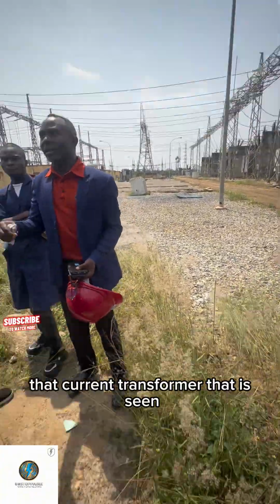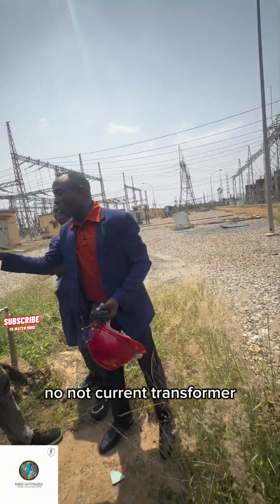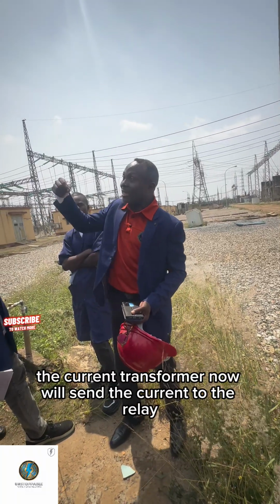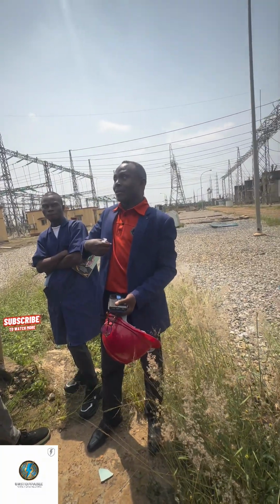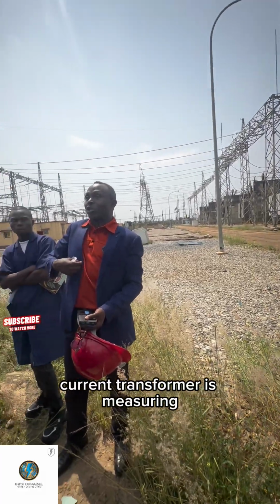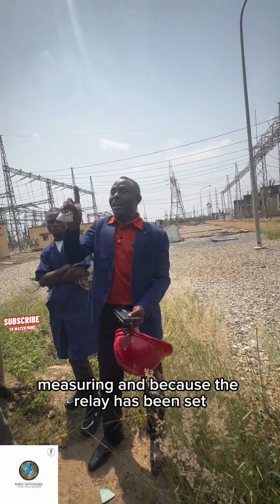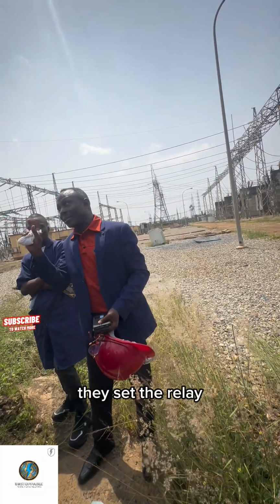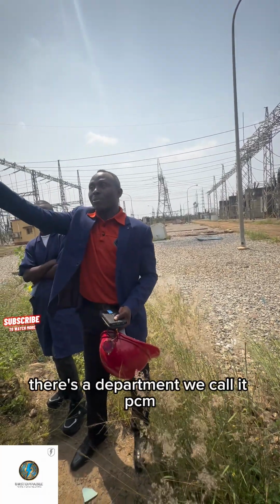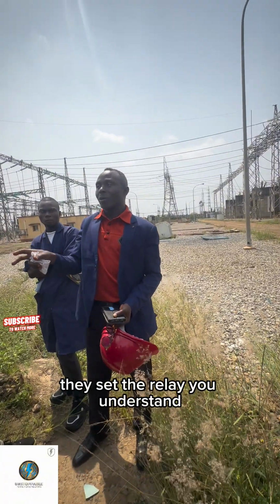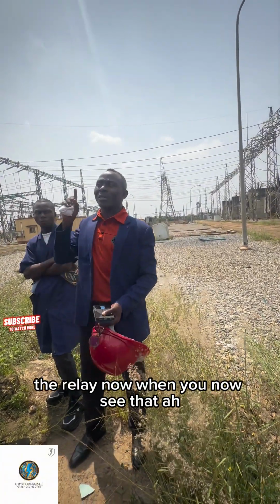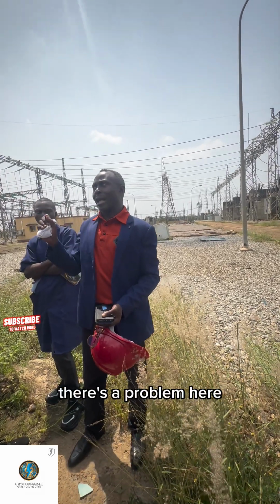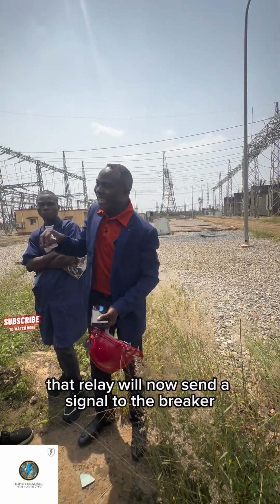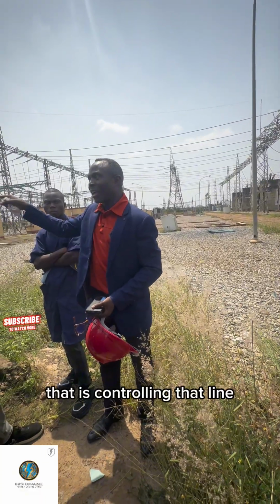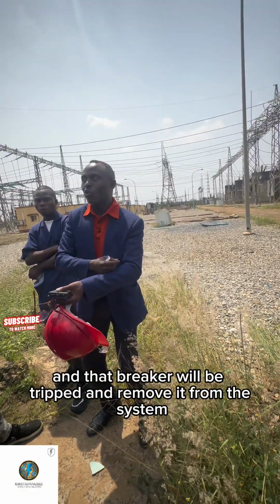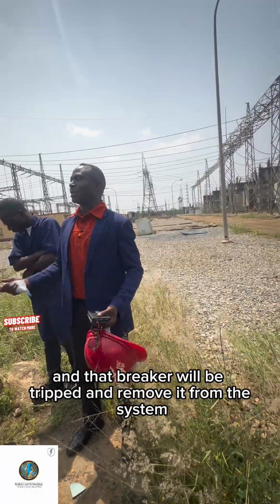The current transformer now will send the current to the relay. Okay. The relay is seeing what the current transformer is measuring. And because the relay has been set, they set the relay. There's a department, we call it PCMA. They set the relay. You understand? The relay now, when it sees that there's a problem here, that relay will now send a signal to the breaker that is controlling that line. And that breaker will trip and remove it from the system.